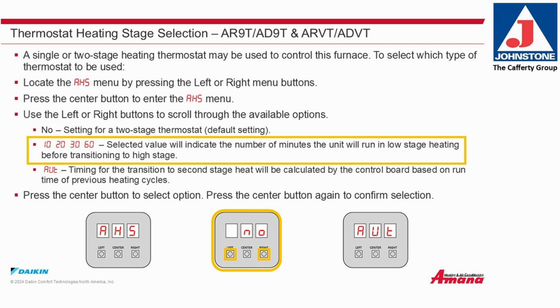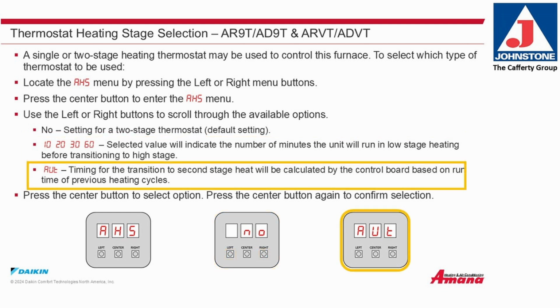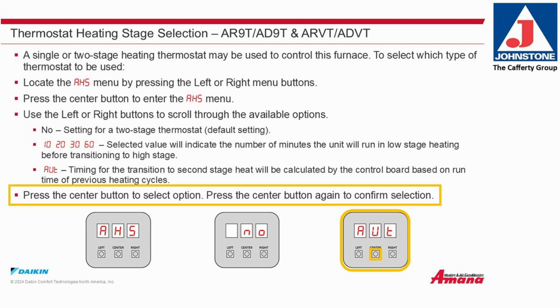10, 20, 30, and 60 selected values will indicate the number of minutes the unit will run in low-stage heating before changing to high-stage heating. AUT, or automatic timing for the transition to second stage heat, will be calculated by the control board based on the run time of previous heating cycles. Press the center button to select the option. Press the center button again to confirm your selection.